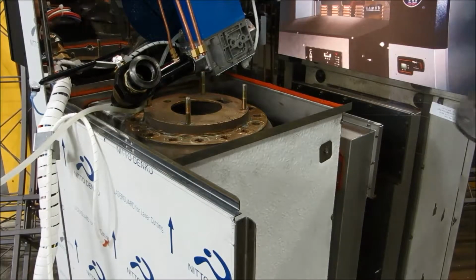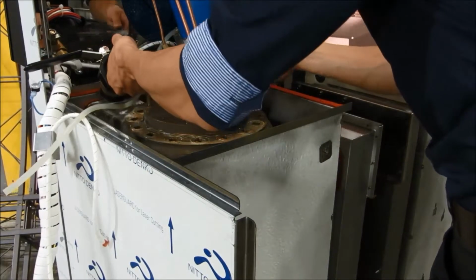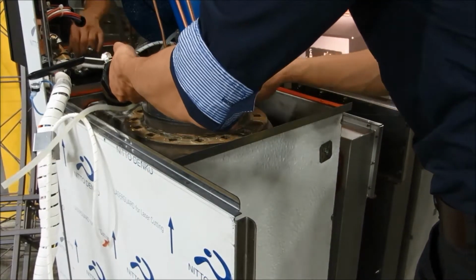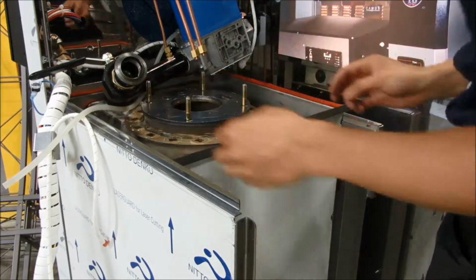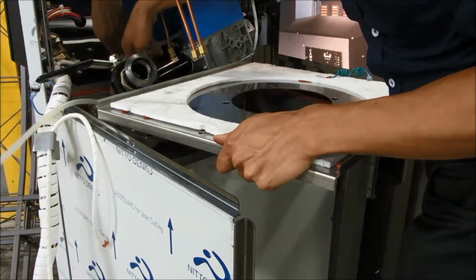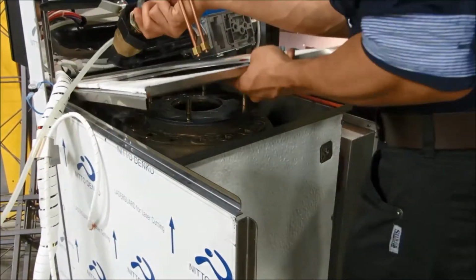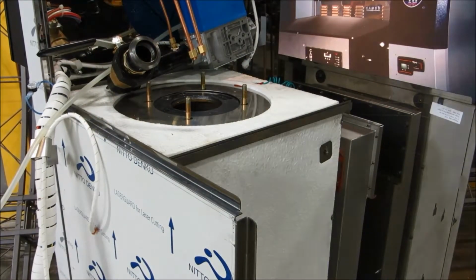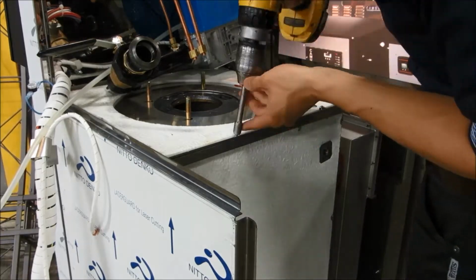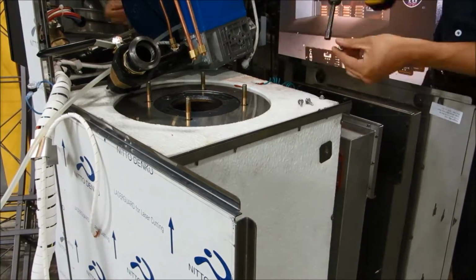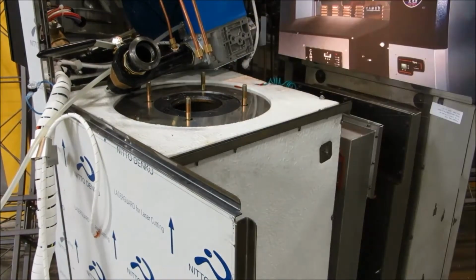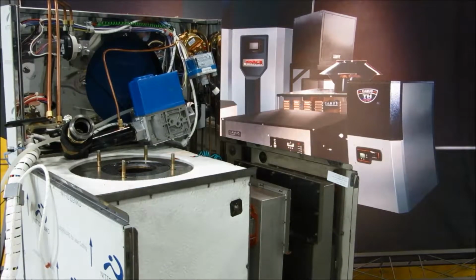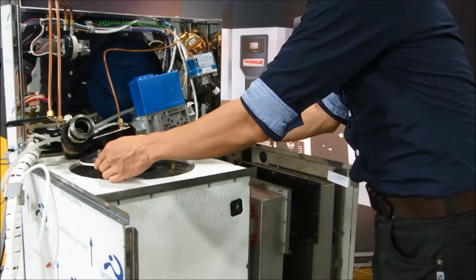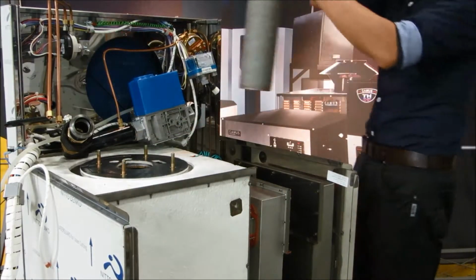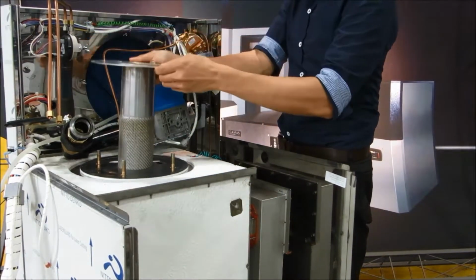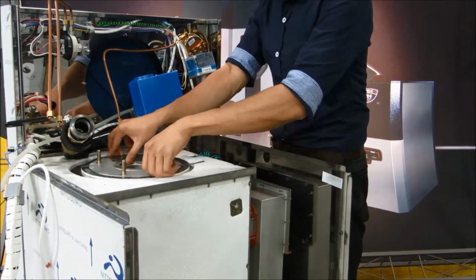Install the graphite gasket on top of the heat exchanger and then screw and replace the combustion chamber top panel. Place the graphite-backed ceramic gasket on top of the combustion chamber top panel and insert the burner vertically into the heat exchanger. Place the red silicone gasket on top of the burner and install the blower.